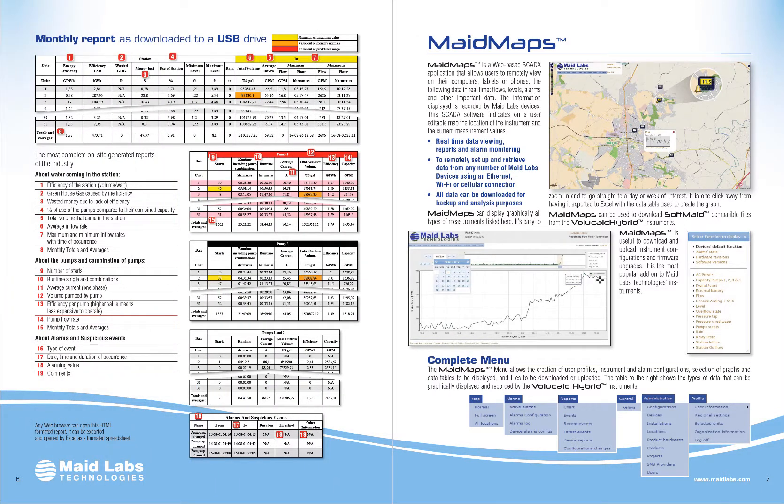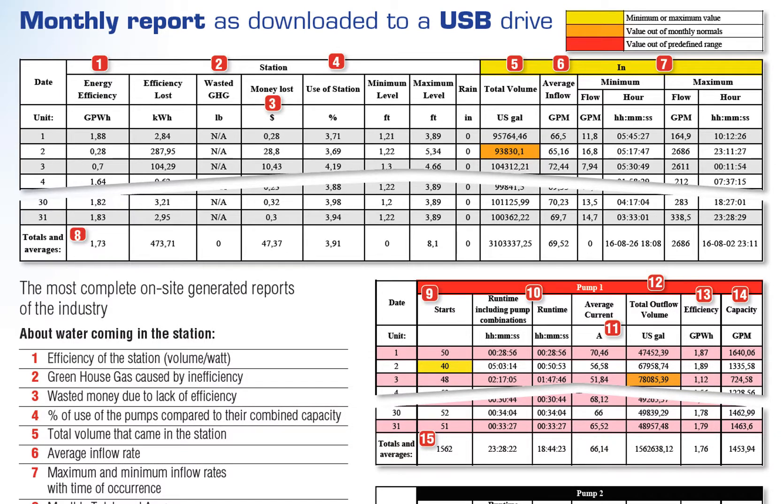The VoluCalc Hybrid generates reports directly on a USB drive or accessible remotely. If you put your USB drive inside the instrument and ask for the monthly report, it will show you the efficiency of the lift station, and mostly the percentage use of the station — which is the volume that went through compared to the maximum volume that could go through if all the pumps were on 24 hours a day. That is the safety margin you have. It also shows the minimum and maximum level, how much rain you had if the rain gauge was connected, how much volume went through the station on each day, the average flow rate, and the minimum and maximum values with their times. Of course you have averages and totals for the entire month.